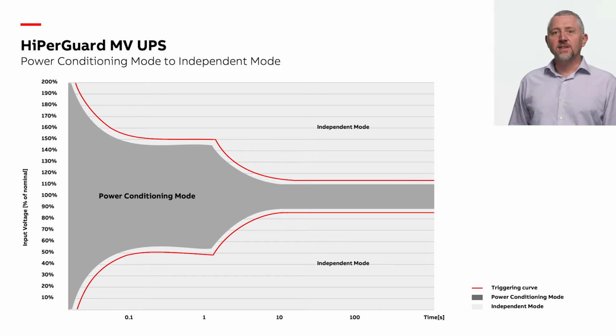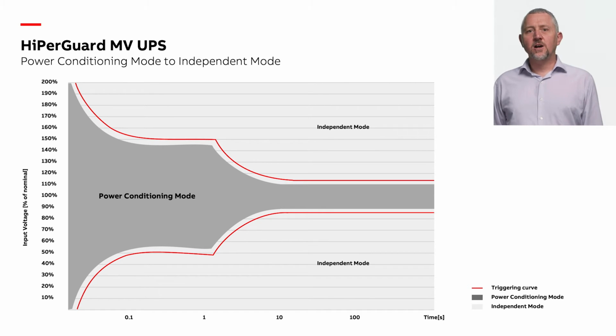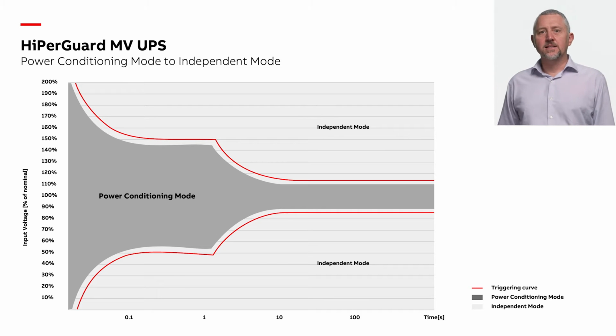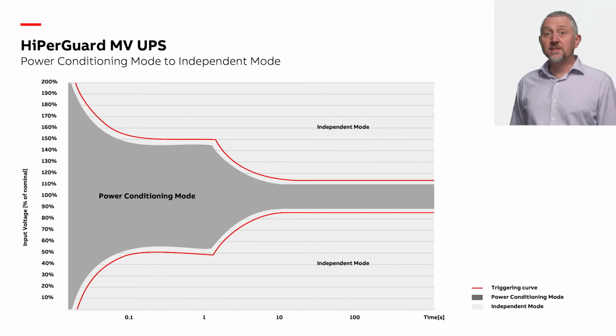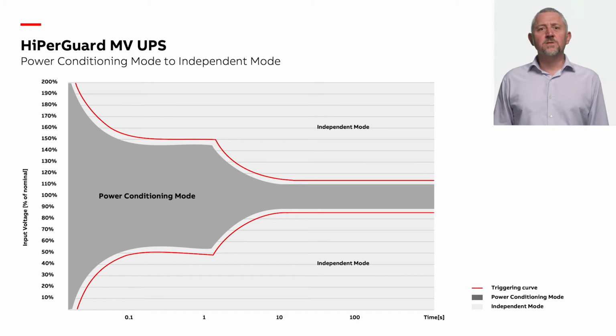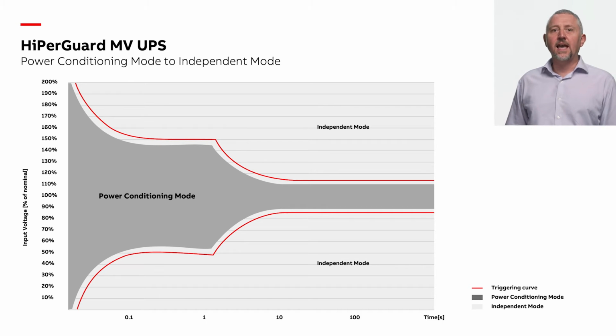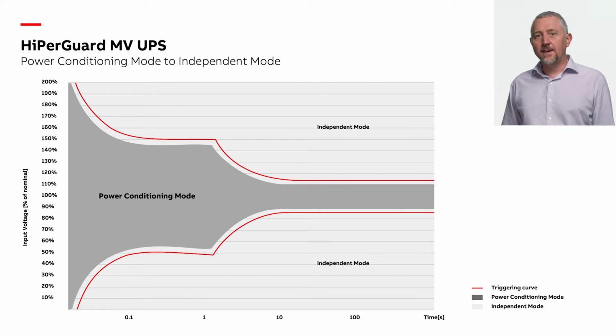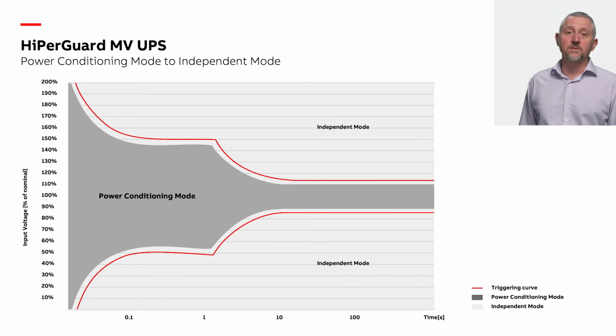This graph here shows how the input breaker is managed. The time it takes to switch between independent mode depends on the input voltage. The deeper the sag, the quicker the switch. The HiPerGuard can stay in power conditioning mode for an extended time if the input voltage remains between 85% and 115% of the nominal. For voltages between 90% and 85%, the UPS is ready for transition, reducing the phase shift. If the voltage drops below 85%, the HiPerGuard syncs to the grid and quickly opens the input breaker. The MV breaker takes about 70 milliseconds to open.